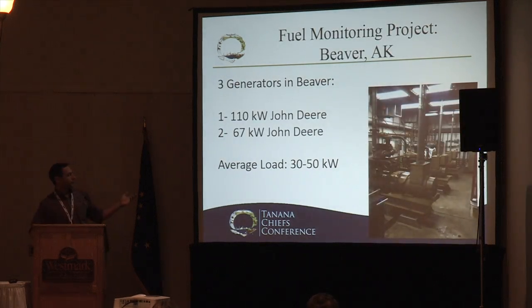So with this in mind, we did a fuel monitoring project. We had some energy efficiency conservation block grant funding in Beaver. Beaver is one of the communities we work with that's struggling, that doesn't have that backdrop of engineers down in Anchorage. They've got Beaver Joint Utilities, owned by the tribe, with 3 fairly new gen sets that the State of Alaska, AEA, put in, completed around 2008. They've got one 110 kW John Deere and two 67 kW John Deeres, and their average load is right around 30 to 50 kW.